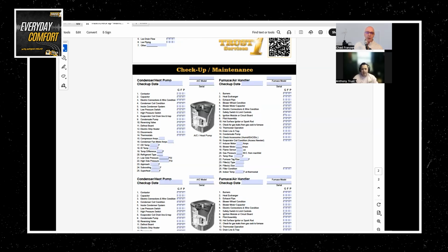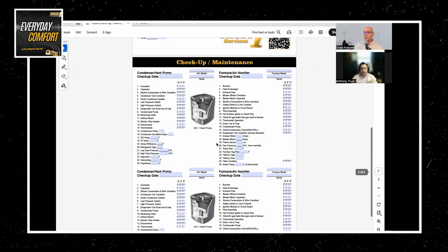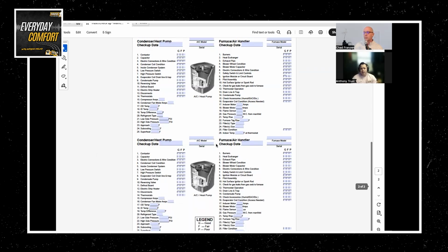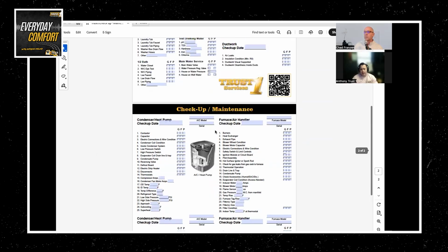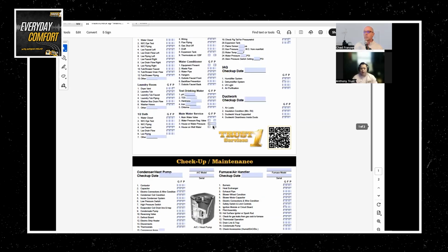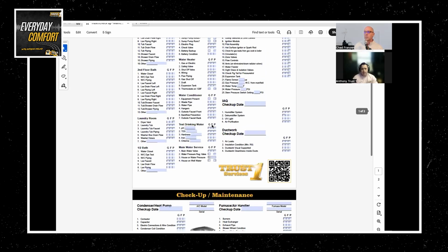So also regarding furnaces, you're checking temperature rise, motor amps, and electrical connections. Tell me about that and why those matter. Yeah, so whenever a motor of any kind is pulling too much power, that means there's something going on with it. And then sometimes there's a capacitor, which is basically a battery pack that gives a charge to those electrical components so that they can start up correctly in the beginning. So those can start to wear out, causing more stress on that motor, and then increase utility bills because it's working harder. And then those components can start to fail.